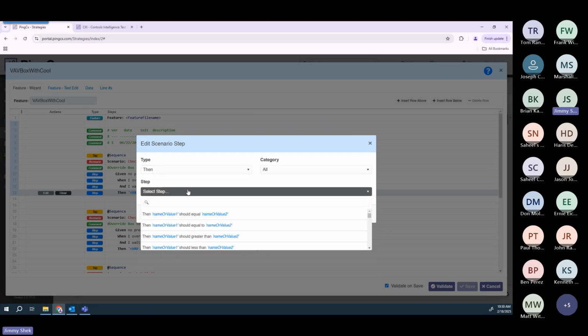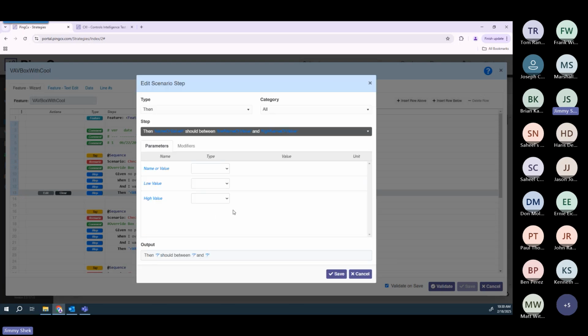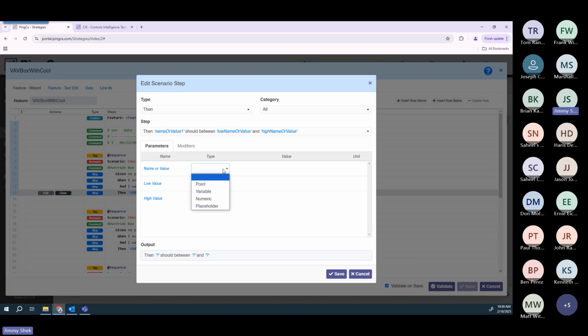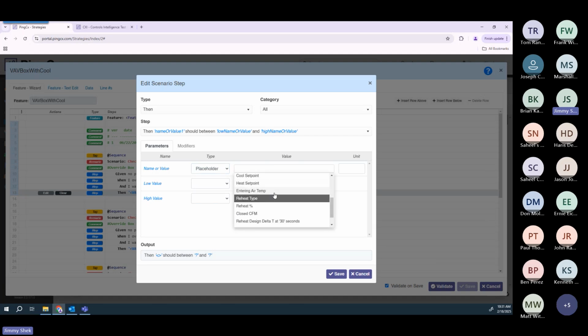Whereas the thens are your assertions, your checks, where you're checking something is equal to something, or checking something is between multiple values. You can select that step, and then the UI will essentially guide you on how to populate the parameters for that. So whether you're selecting a placeholder in the file, right, or you're selecting a specific point, the UI prompts you and guides you in selecting the points from the system. As mentioned earlier, we leverage those database files from each one of those front-end platforms. We parse those devices and points, and we make them all available here through the UI.